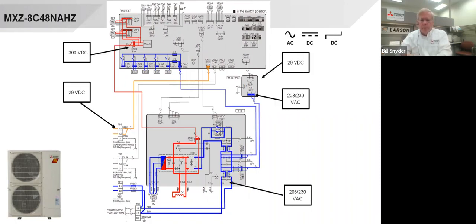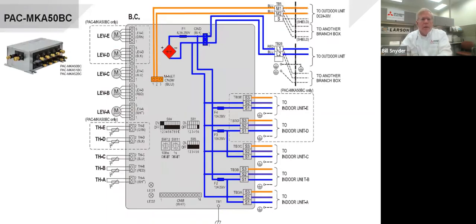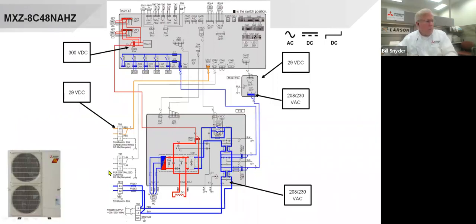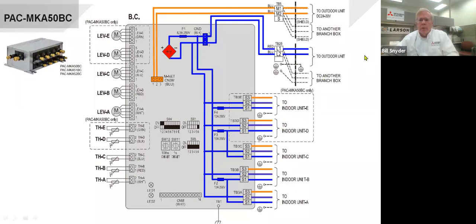And again, these are your voltages. And this is 29 volts that comes down from this board here, through here, all the way down for the communication voltage. And this would be the branch box it goes to. Let me go back here. If you can see this, down in this area, this is where you power the branch box. And on this next screen, this is where that is coming from the outdoor unit to the branch box here. And the communication wires we were showing on the other screen come in here as M1 and M2, and they come in and communicate. That's the 29 volts coming in here.